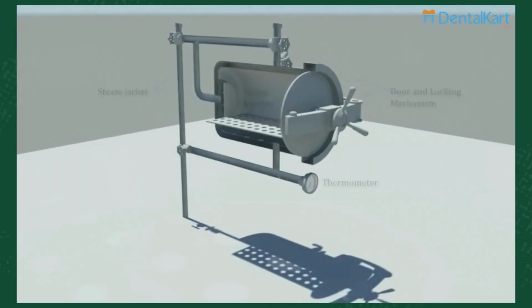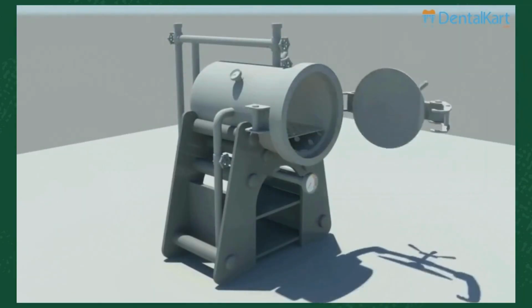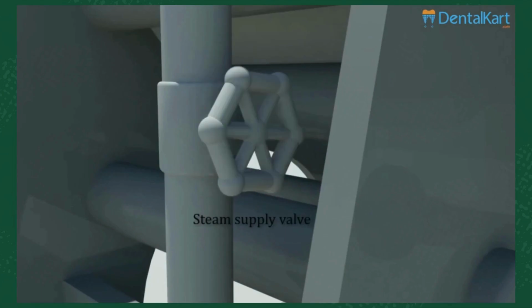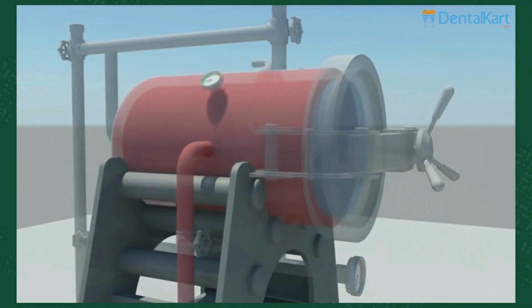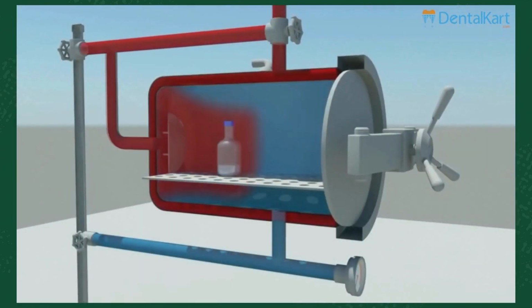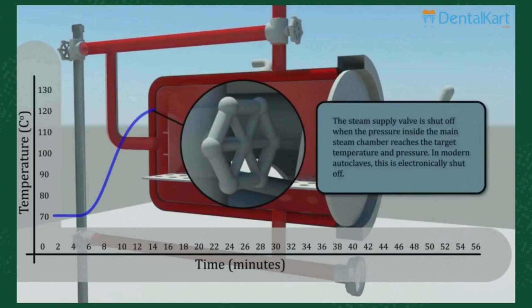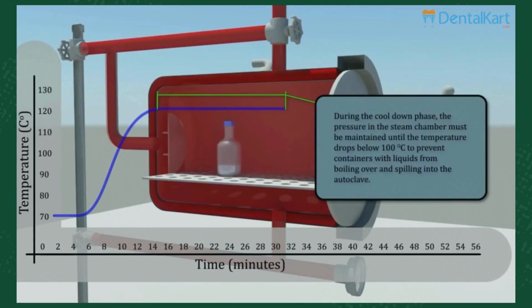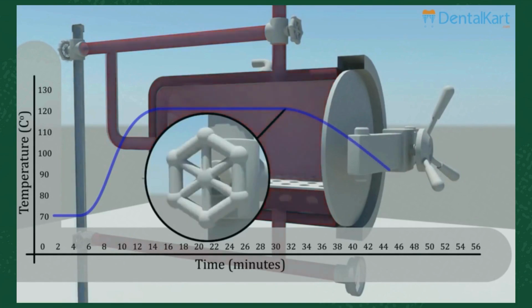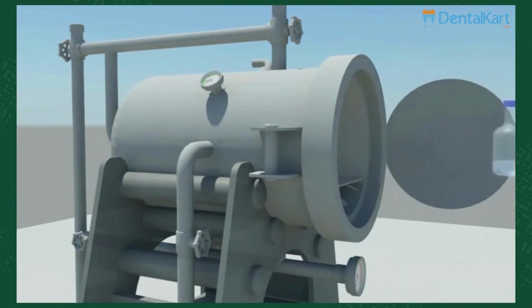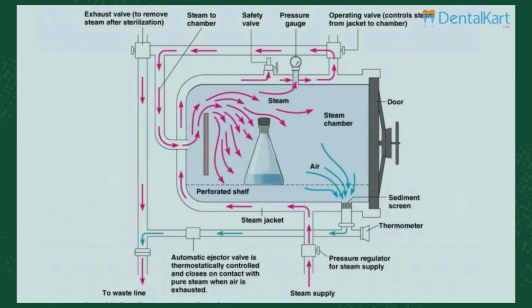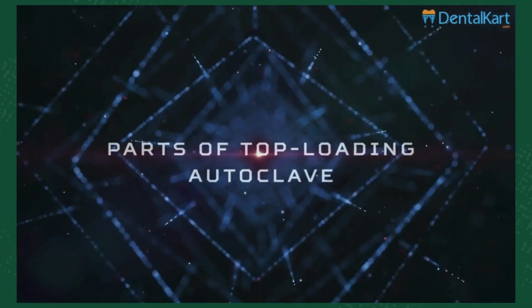This autoclave works on the principle of moist heat sterilization. High pressure inside the chamber increases the temperature of water to generate steam for the sterilization of instruments. The higher pressure also ensures rapid penetration of heat inside the drum to sterilize. The moisture present in the steam causes coagulation of proteins of microbes, causing irreversible loss of their activity and functions.